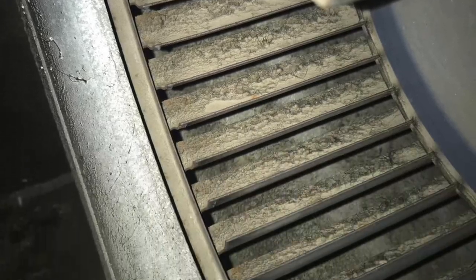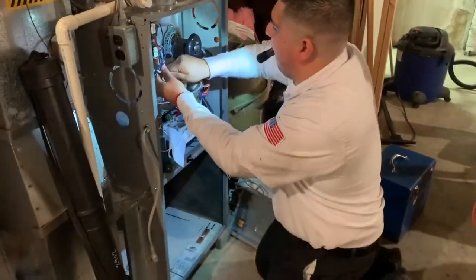It's burning improperly and something else has also failed. You could have a very dirty furnace with rust, dust, and debris on the burner causing impingement, generating high CO levels in the exhaust — and then a flue that's plugged or rusted off and venting into the basement or attic, or a problem with the heat exchanger. But it's got to be more than one thing. Typically one thing alone isn't going to be an immediate problem.